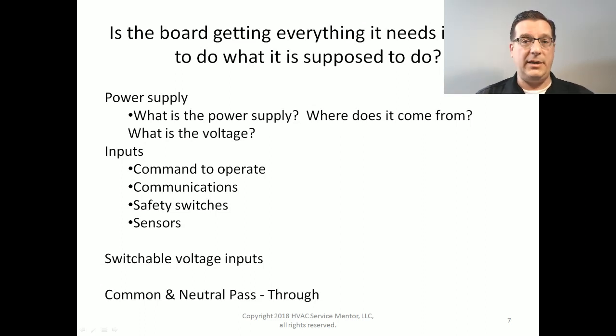Next, is a board getting all of the inputs that it needs to operate, such as a command to operate, something that tells it go. Most of our control boards are powered up all the time, and they're waiting for that go signal to come. So is it getting it, or is it not? What is it, and where does it come to? If it's a communicating control board, is it receiving the right communication from its cooperative controller? Any safety switches, such as limit controls, end switches, pressure switch controls, refrigerant pressure controls, temperature switches, all of these things are types of inputs. And then also sensors. Some control boards are going to have temperature sensors, analog sensors attached to them that aren't just an open and closed switch. So are the switches and sensors there? Are they operating correctly? Are they giving the right information to the board? These are all things that affect how a control board works.